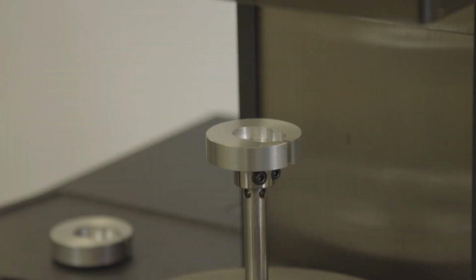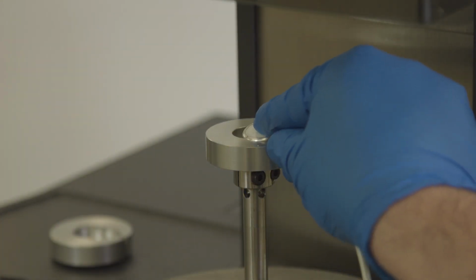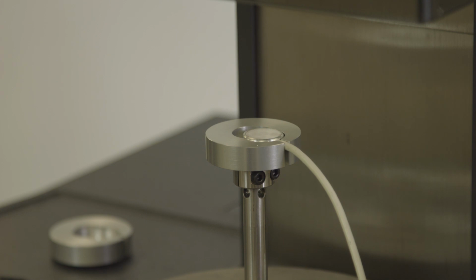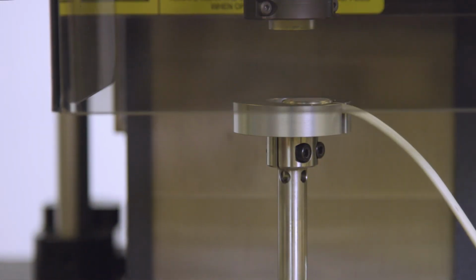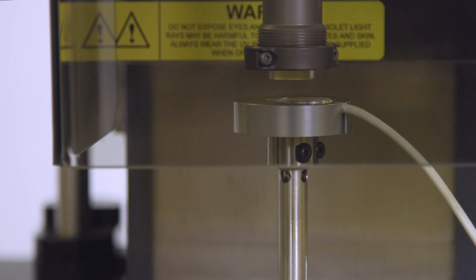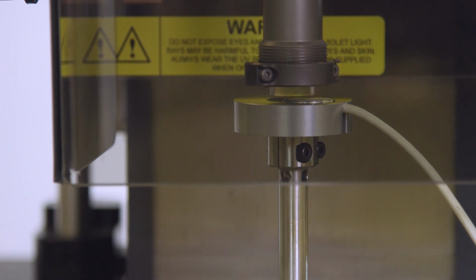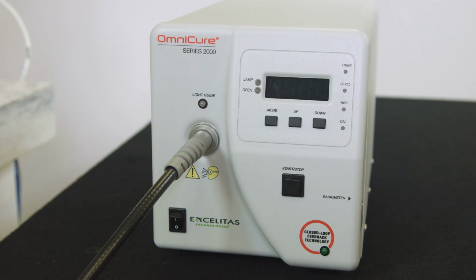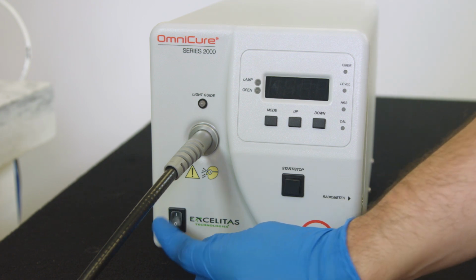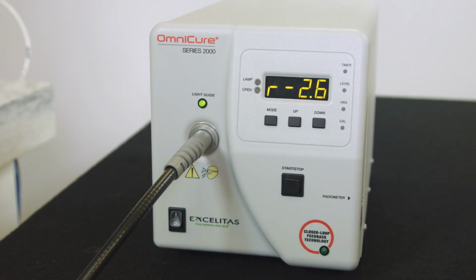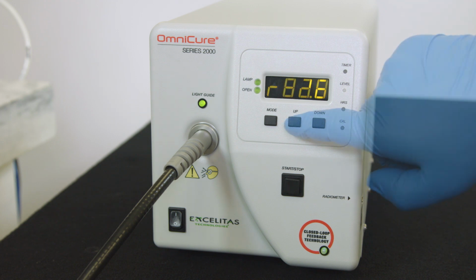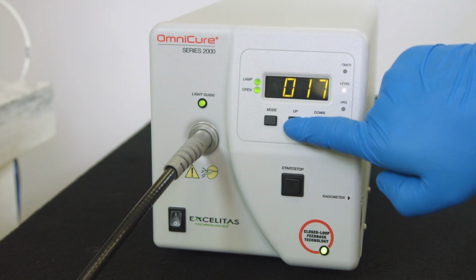Attach the UV sensor geometry to the disposable plate and socket the UV light sensor off-center. Once this is in place, apply approximately 100 grams of axial force with the control panel. Power on the light source and let the bulb warm up. This can take several minutes. When the light source stops flashing, set the power to 25%.